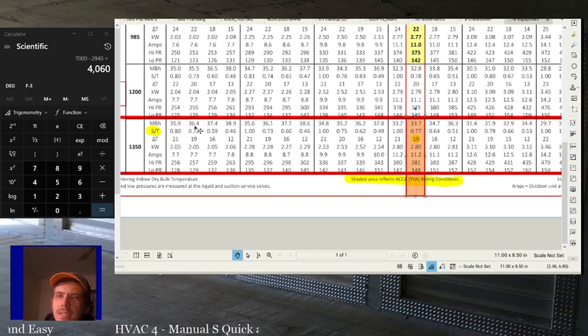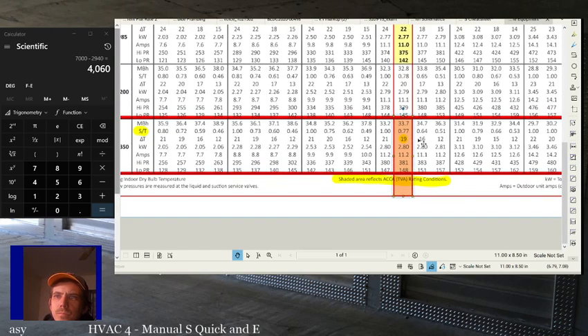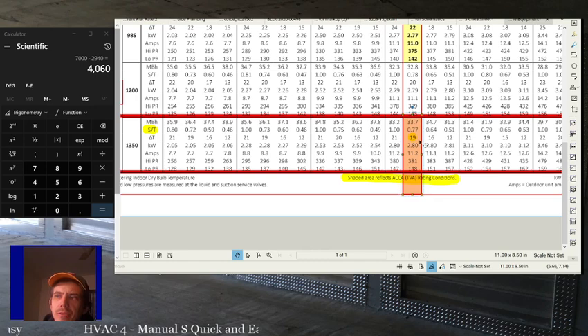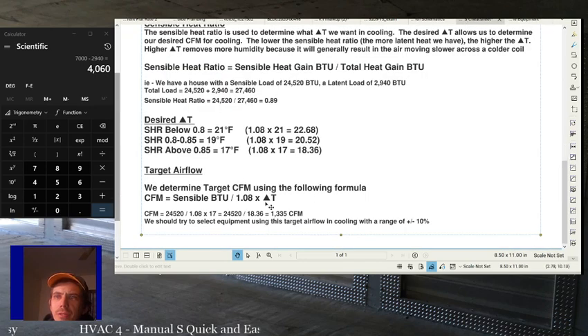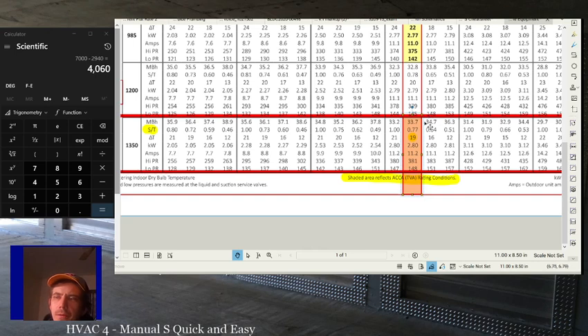But this is how Goodman does it. This is one thing that changes from manufacturer to manufacturer, how they present total versus latent load. But in Goodman's case, they give you the sensible divided by the total. So they basically give you the sensible heat ratio, and that's what gives you how many BTUs of each you have. They give us the delta T that you're going to have, and this is a 19 degree delta T, which actually, if you go back to the cheat sheet, is too high, right? That's a 19 degree delta, and we want a 17. But once we're done picking it, you'll see that it still works out. And then they give you a bunch of other data that's basically irrelevant, and as far as Goodman goes, the kW, the amps, yada yada, we're not too worried about that.